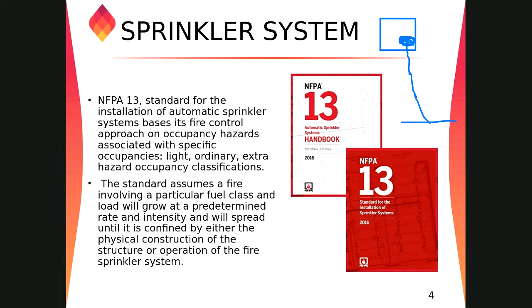So this is the chapter. Chapters 1 to 4 are the foundation chapters. Chapter 5 is for the classification of occupancies and commodities, right, which is very important for designing a sprinkler system. Our design of a sprinkler system starts from chapter 5, because we have to select a hazard, whether it's light, ordinary, or extra hazard, based on various parameters, and we have to select the classifications, right? After that, chapter 6 covers the hardware, right? So it's generally talking about the listing requirements, approvals, and all those criteria, and the types of systems used and all.